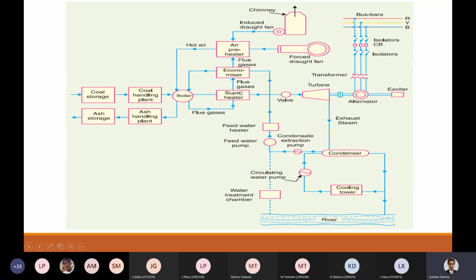In the economizer, the flue gases which are available at the output of the superheater will pass through. The role of the economizer is that the water which is already hot, coming from the feed water heater, is heated again so that it becomes even hotter with the help of these flue gases before feeding into the boiler. I repeat, the flue gases available at the output of the superheater, after we have dried and superheated the steam, will pass through the economizer, where the hot water coming from the feed water heater is heated again, so that this water gets further hot, and only then will it be fed into the boiler.